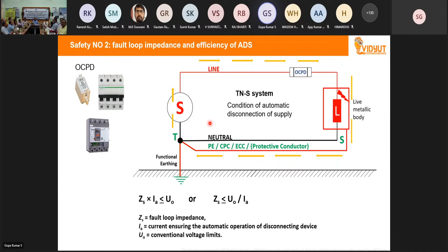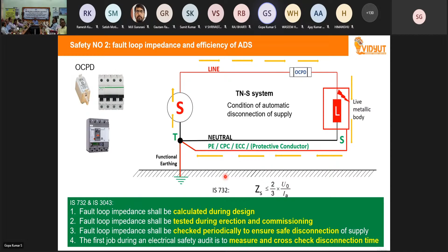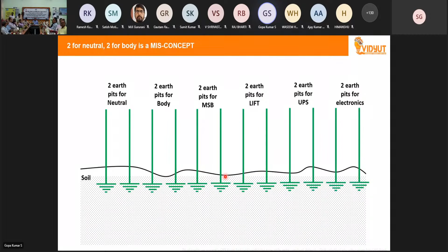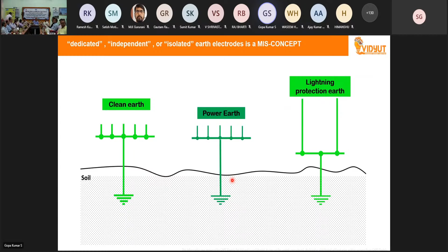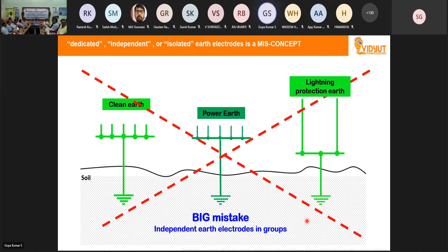In our standards, we have written to calculate the fault loop impedance, test the fault loop impedance, and do it during safety audits. But unfortunately, this method is quite new or not followed in India. When it comes to earthing, which is a very important subject of electrical safety, electrical engineers sometimes work like farmers. They dig more and more holes into the soil and put more and more chemical and earth electrodes. There is nothing like 2 for neutral, 2 for body and all. Earthing, like clean earth, power earth, and all these separate earth electrodes, is also a wrong method. This is a big mistake.